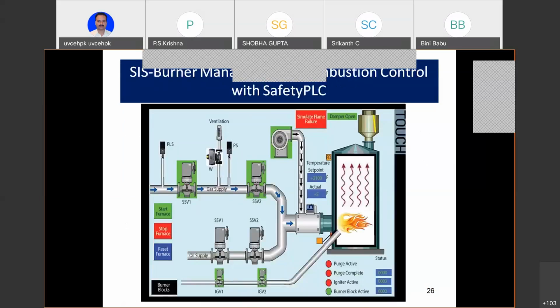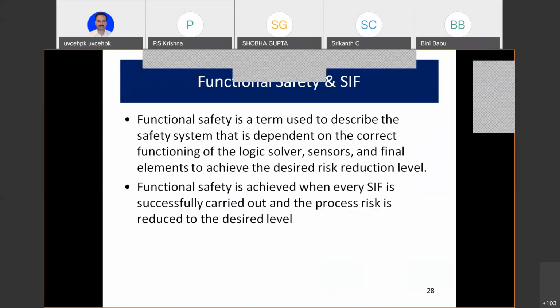This functional safety system is a very important definition for you, and it's better I read it. Functional safety system is a term used to describe the safety system. There are several safety systems: fire and gas, systems for spraying from a helicopter, so many things. But this functional safety system is a term used to describe the safety system that is dependent on the correct functioning of the logic solver, sensors, and final control elements. In that flame sensor, if the sensor was not proper, it may not be sensing, or it may give a false reading that the flame is on when the flame is not on. So the sensor, everything has to work like a proper orchestra.